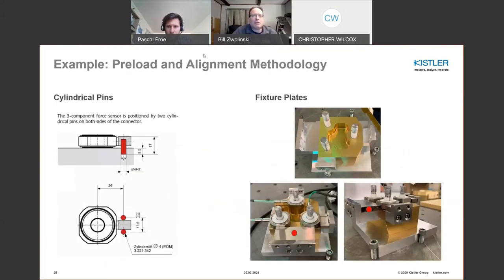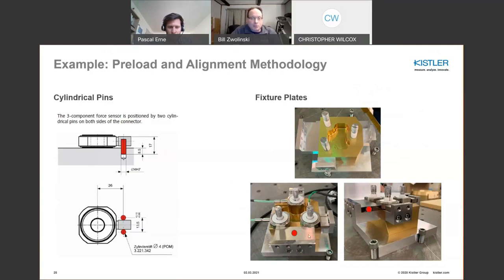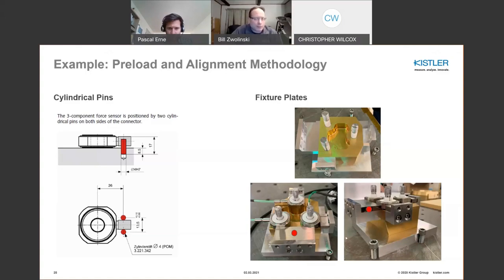A practical example of sensor alignment: you want to ensure the sensor does not turn during preloading. One approach is to use dowel pins at the connector — two pins surrounding the connector — to constrain rotation. Another approach shown here uses metal flats or pieces aligned with the sensor flats; as you torque them down, the sensor cannot rotate. Once the fixture is fully assembled, these alignment pieces are removed and are no longer part of the vibration fixture. Creating an innovative fixture that allows proper preload is quite important for mounting and installation.